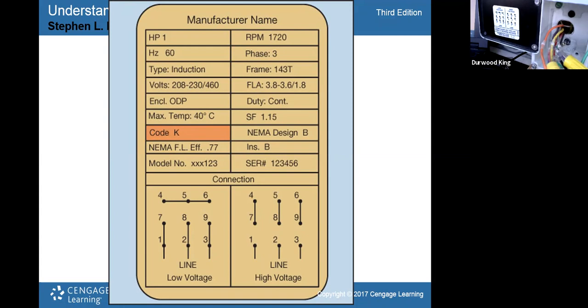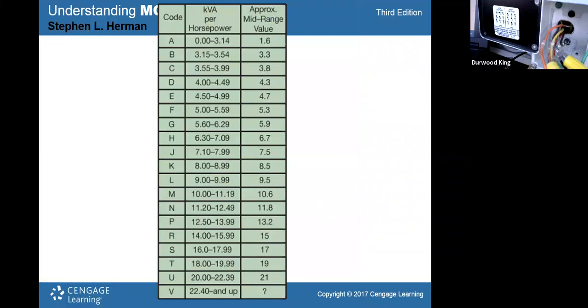Actually, the code letter, if you look right here, this is showing you: if the code letter is K, then you would multiply that kVA, which is kilovolt amperes, which is like wattage. kVA is like saying wattage because it's volts times amps. They put a K in there, it's thousands of volt amperes or thousands of watts. Volt amperes is like saying watts. So if it's a K type code, then you would multiply this.